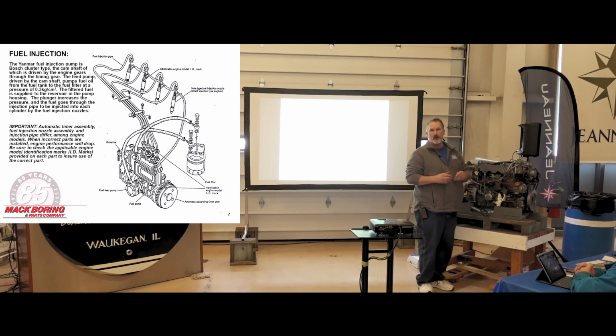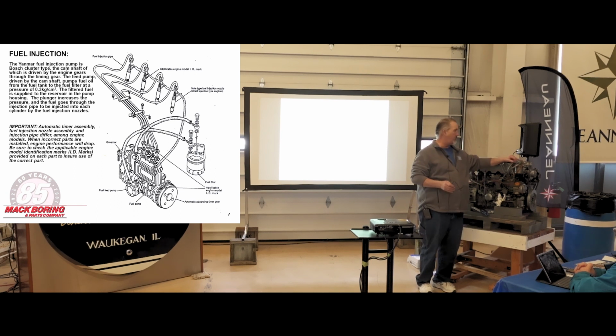A lot of people don't know this, but on a Racor, there's a little knurled knob on the top of it. That's actually a pump. People think it's just a vent, it's not. You unscrew that, you can pump it up and down. But unless you have a valve or a connection open, you're doing no good. You have to let the air escape. So once the air has escaped, you close it down.